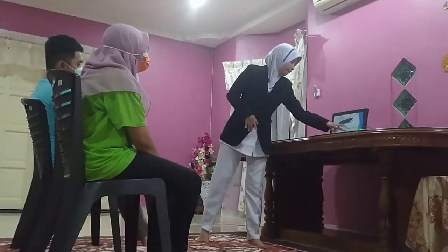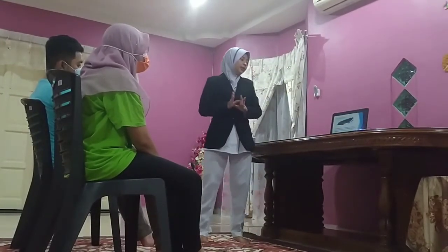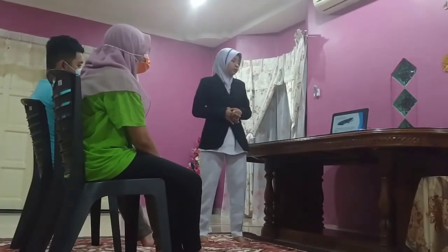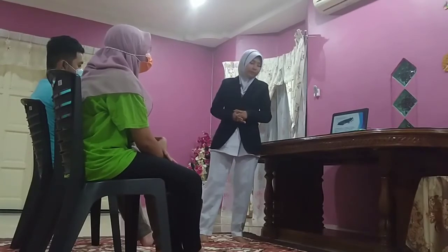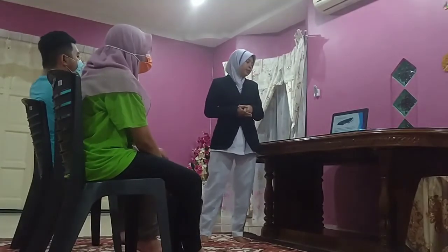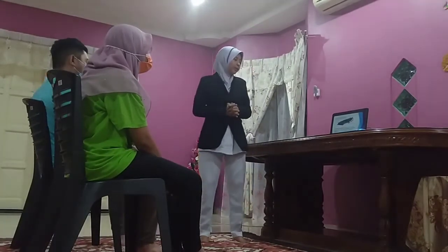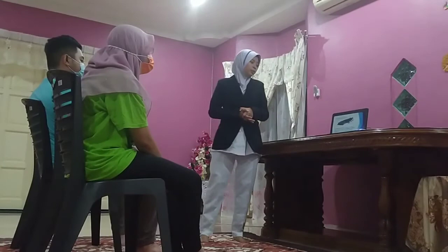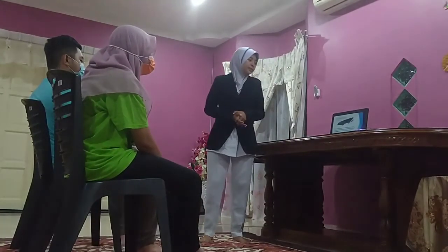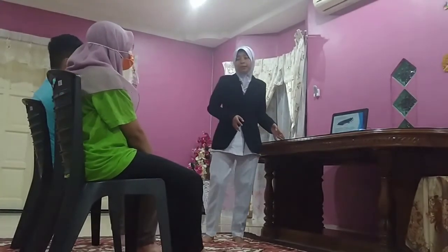Okay, this is the vacuum mattress. A vacuum mattress or vac mat is a medical device used for immobilization of patients, especially in cases of vertebra, pelvis or limb trauma, especially femur trauma. It is also used for manual transportation of patients for short distances. It replaces the stretcher. This is a vacuum mattress.